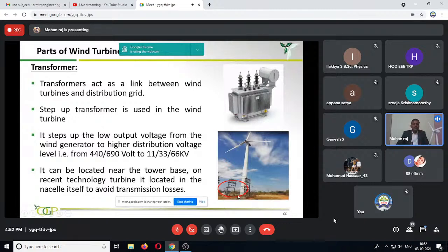So the 11 kV, 33 kV or 66 kV cable will go up to the nacelle to avoid transmission losses. Because when the voltage is very low, the current will be high. If the current is high, then the copper loss of the cable is so high. So to reduce the current, you need to increase the voltage. For that purpose only we are using the transformer. So as I said, it can be located near the tower base, and in recent technology turbines it is located in the nacelle itself to avoid the transmission loss.